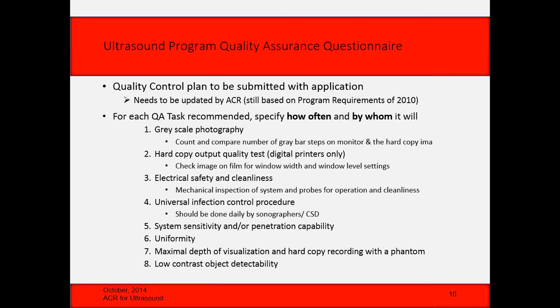Uniformity of the image, so again, that is the contrast of a received echo. The same received echo can be displayed the same on the left and right side of the image, top and bottom, that kind of thing. The electromechanical cleanliness of the system in the probes. And then this is one that's different from the other 8 in the ultrasound program.